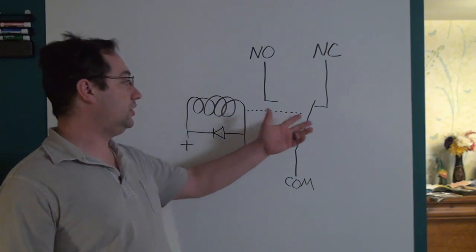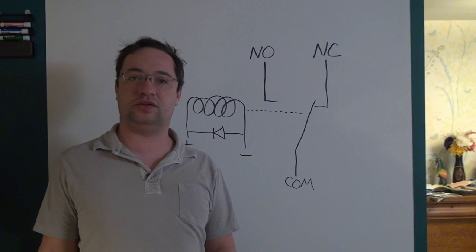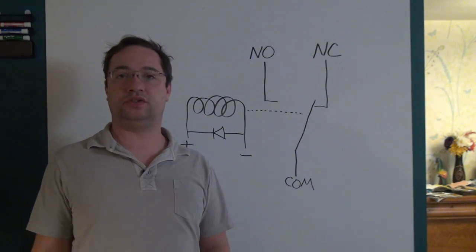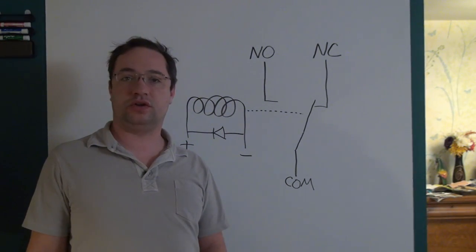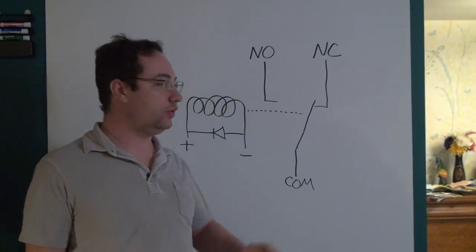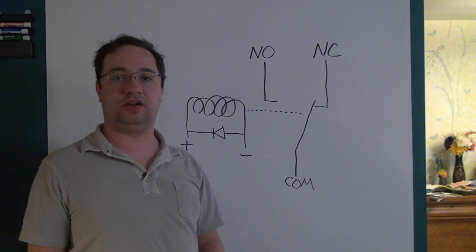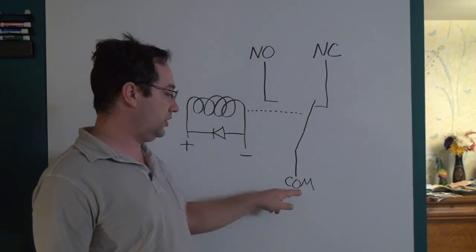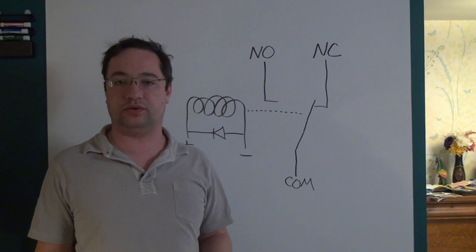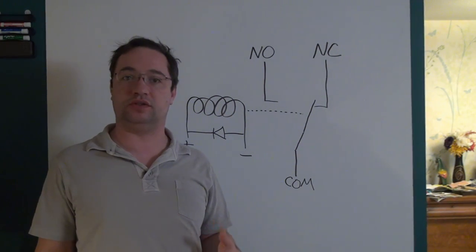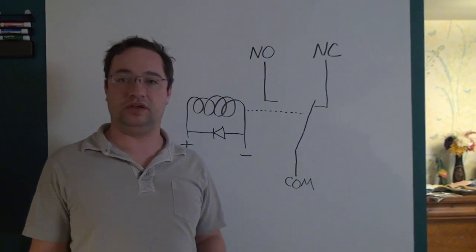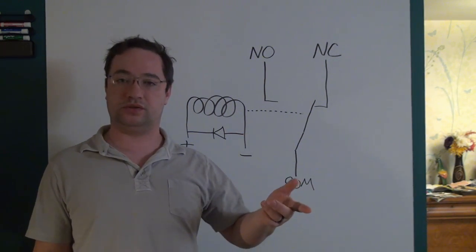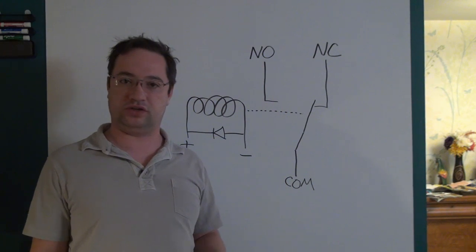Moving on to the hot side of a relay, it probably has the greatest amount of ratings and they are the most misunderstood. The first rating is a voltage rating, which refers to how much voltage the hot side can tolerate between, say, the normally open and common terminal without getting arc over. The rating is sometimes given in AC, sometimes in DC — and remember that an AC rating will be given in RMS, but the peak voltage is actually higher than that.